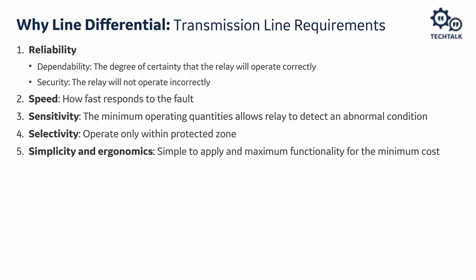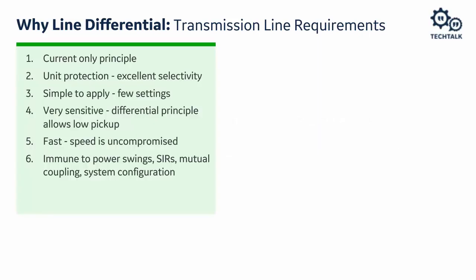The advantages of line differential are essentially the disadvantages of distance. Number one: it's a current-only principle — we don't need voltage, removing the voltage transformer component and increasing system reliability. Second, it's unit protection by definition, operating only for faults within the zone. It's very simple to apply with only a few settings. It's very sensitive, allowing low pickup. Fast speed is uncompromised, and it's immune to power swings, source impedance ratio, mutual coupling, and system configurations.